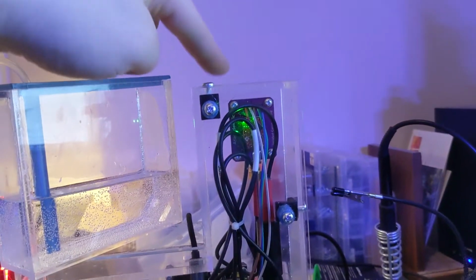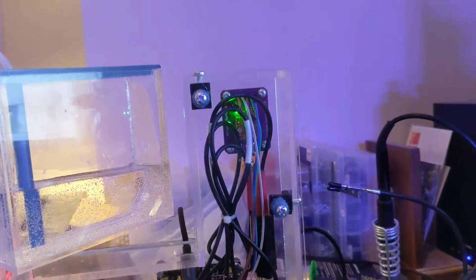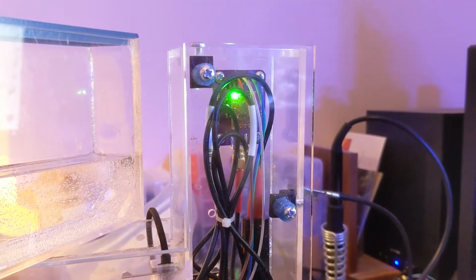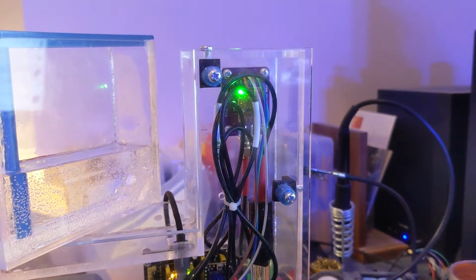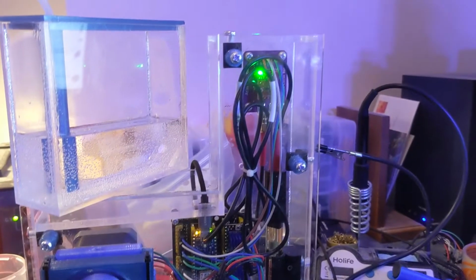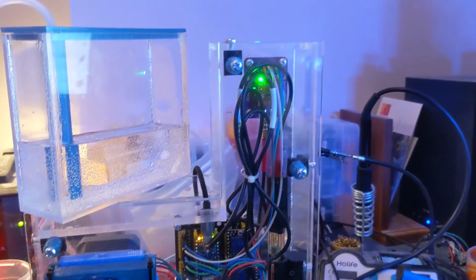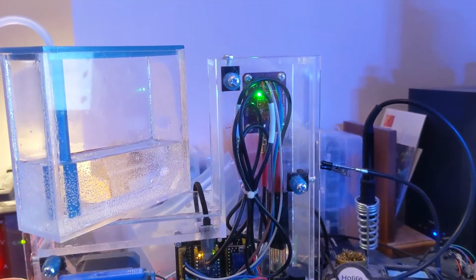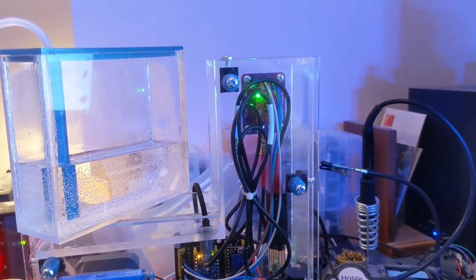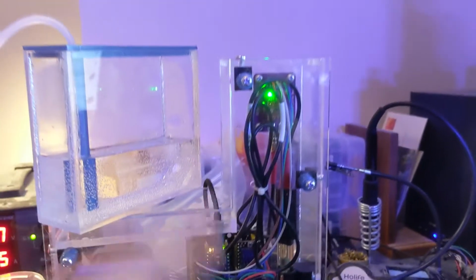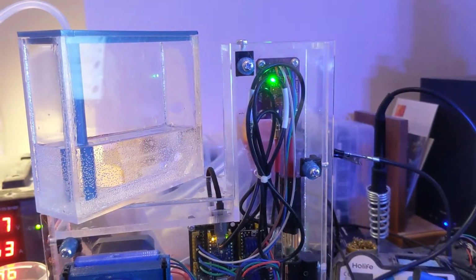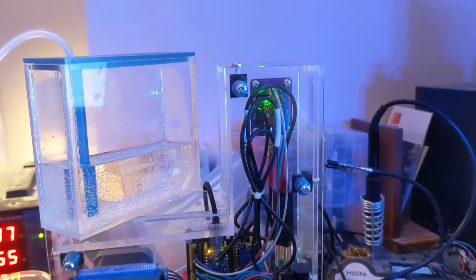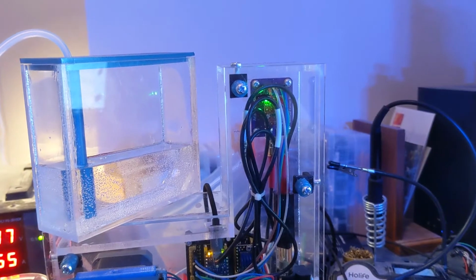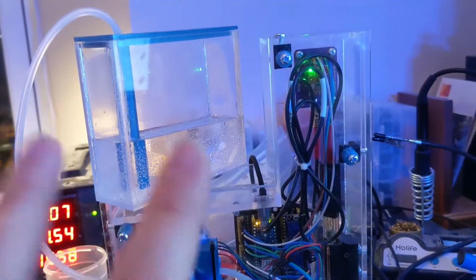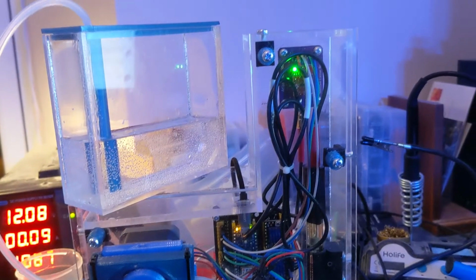This, by the way, is an analog to digital converter one. Atlas Scientific are pretty widely available, probe and board, and they're what I suggest. It is possible to take pH readings using an analog signal amplifier, and those kits tend to be a bit cheaper, like a lot cheaper, like £60 cheaper for the probe and the board together. But I really would not suggest that. I couldn't get an accurate reading on an analog amplifier, given all the other electrical noise that's in here. The analog signal just doesn't cut it.